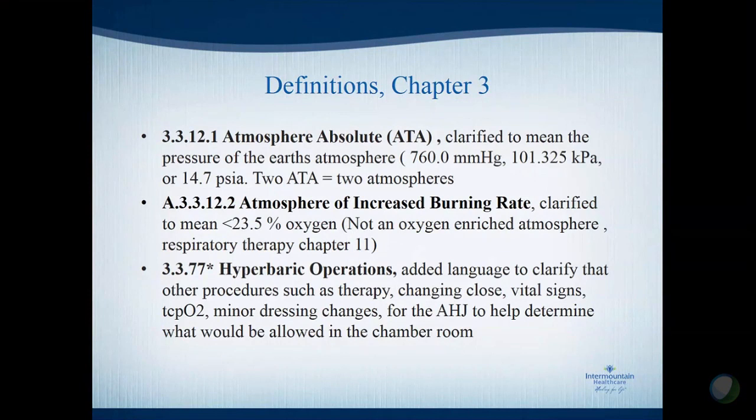But all of the language that's in the respiratory therapy chapter doesn't really apply to hyperbaric oxygen, so we wanted to add that. We put it in an annex note because once you start putting language in the code, it gets really interesting. Different people apply it different ways. So it was sort of put it in the annex, that way it's not required.